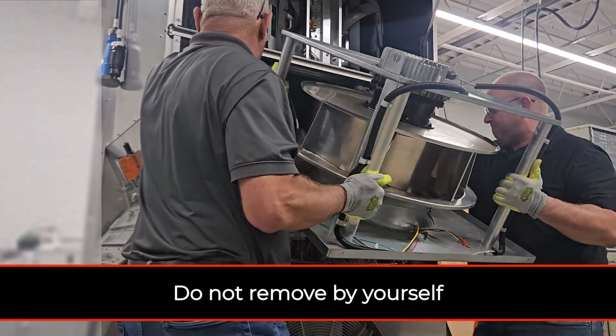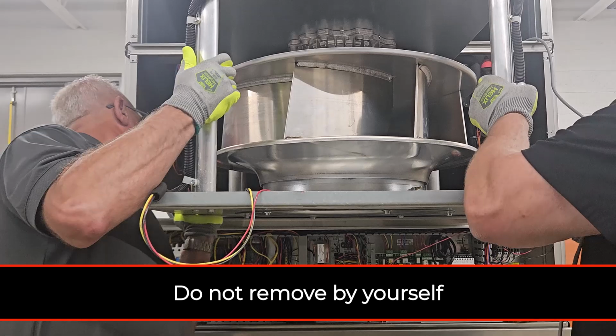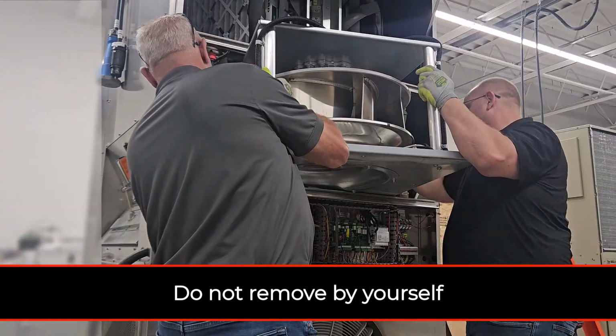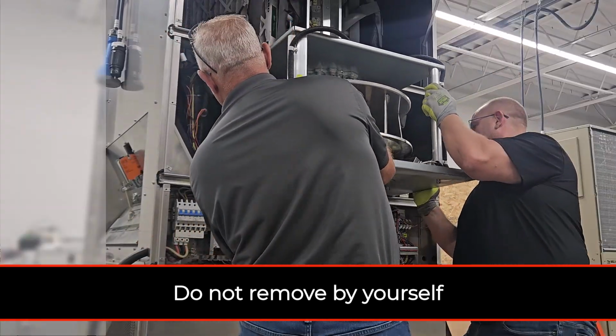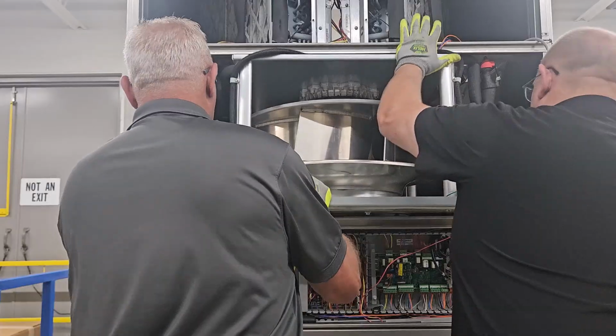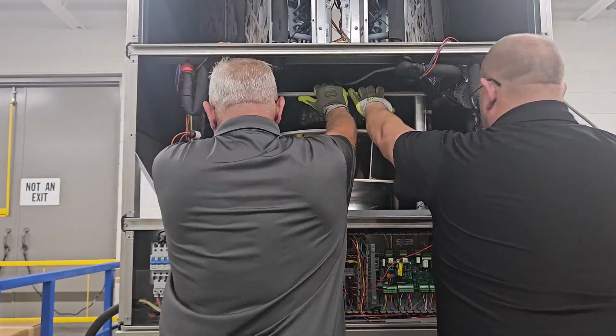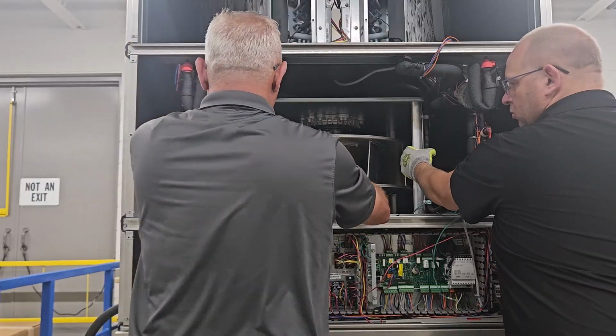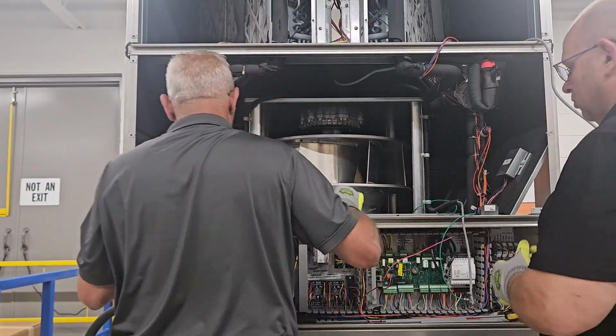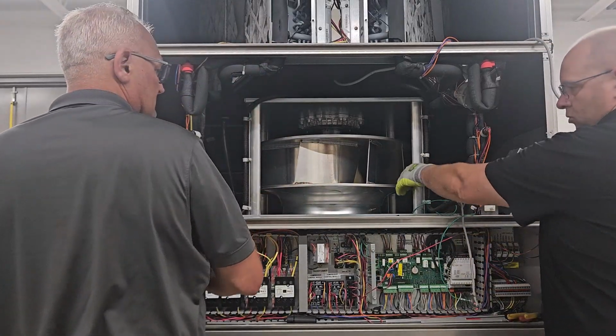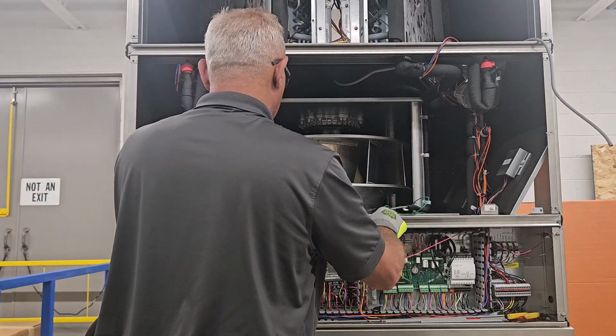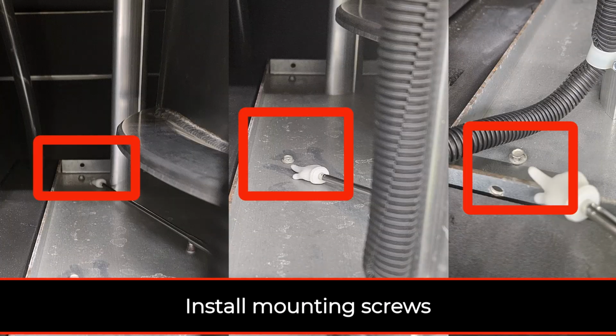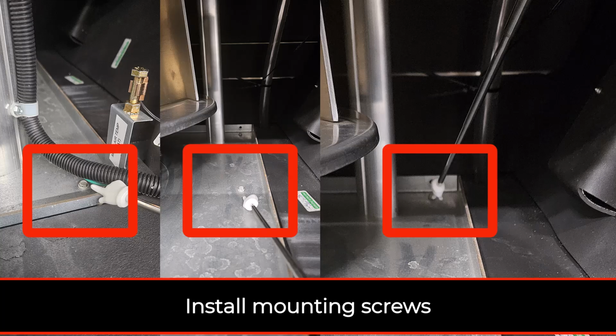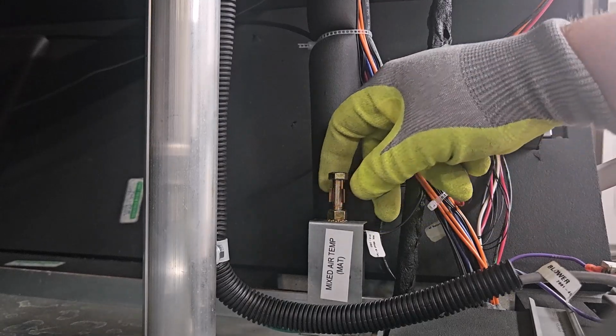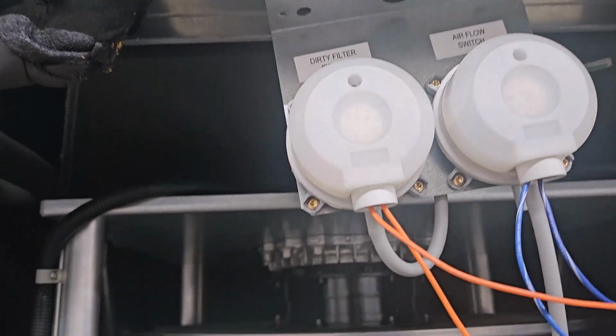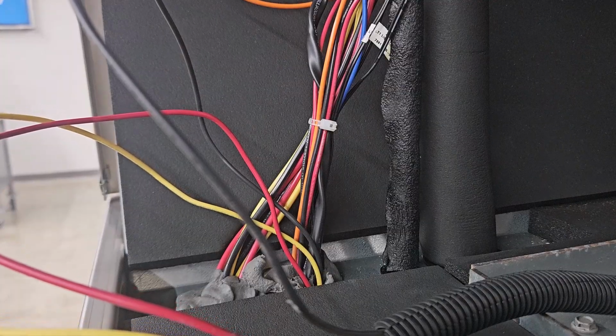After removing the old assembly, use 2 individuals to install the new assembly into the MEGA-TEC housing. You will find installing the motor easier than removing the motor from the blower section. Please note, mounting screws may hold up the installation process. Pushing up on the top of the assembly will help clear these mounting bolts from the frame. Install the mounting screws on the assembly. Attach the mixed air sensor and mounting bracket. Install the fan proofing switch and filter switch.